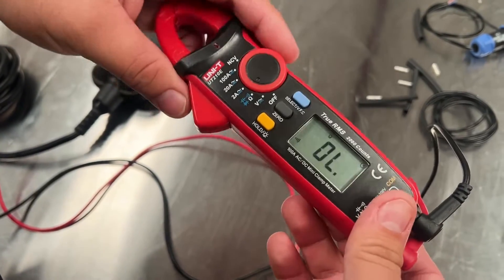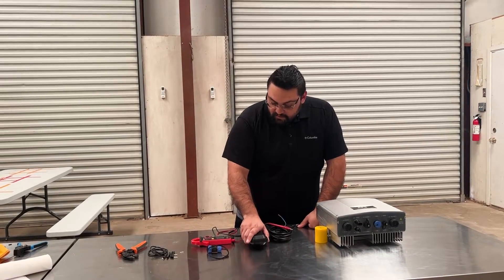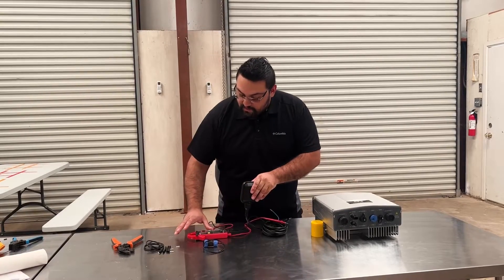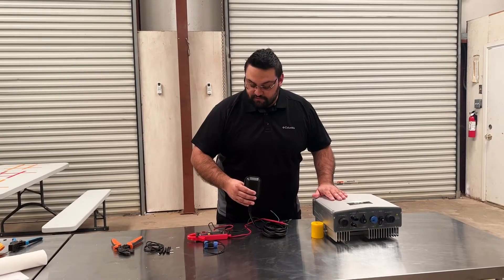Right now it's showing open and it's not making any beeping noise. As your float goes up to the top of the tank, our multimeter beeps showing continuity. This will tell the pump controller to shut off the pump and that the tank is full.